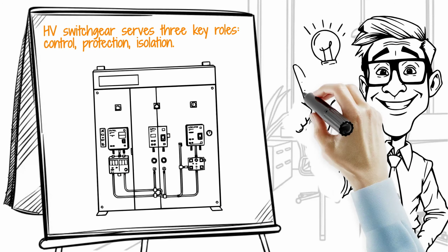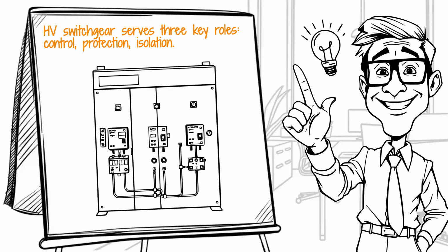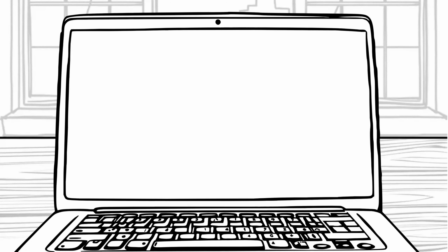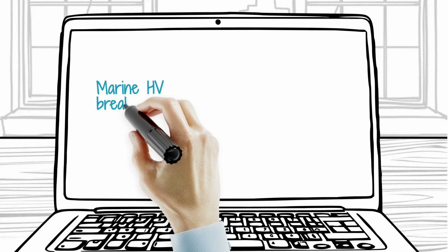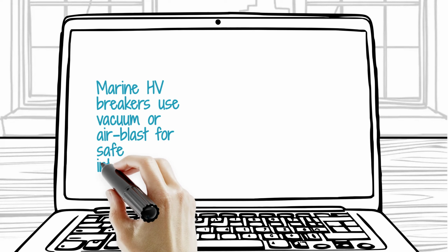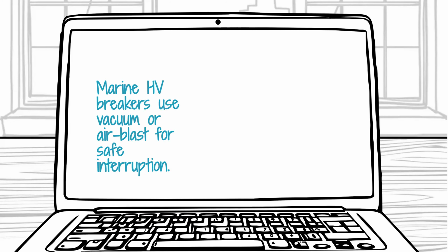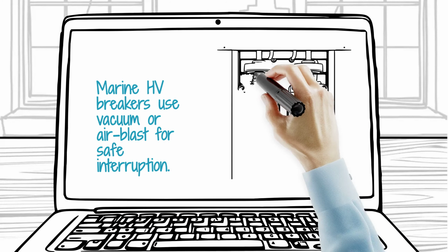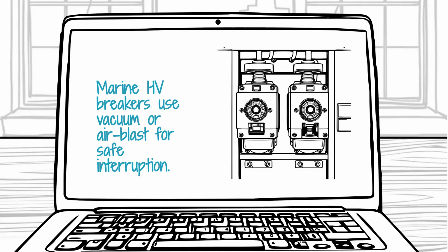The main switching device in HV switchgear is the circuit breaker. These aren't like the little breakers in your house. Marine HV breakers are often vacuum circuit breakers, VCBs, or air blast circuit breakers that use a rapid vacuum or blast of compressed air to quickly extinguish the massive arc that forms when interrupting a high-voltage, high-current fault.